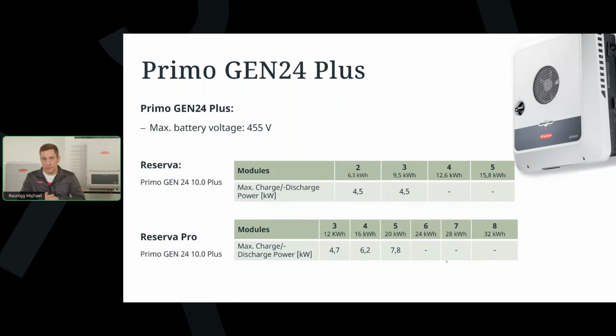Talking about the Primo Gen 24 Plus in detail, since this can be very interesting for single-phase markets, with the Primo Gen 24 Plus series, we have a maximum battery voltage of 455 volts. So that is our top level for the battery voltage, meaning that we get 2 compatible variants with the Reserva system. So with the existing battery system, we have the variants with 2 and 3 modules available. So that means from 6.3 to 9.5 kilowatt hours. However, the bigger systems with Reserva Pro are not compatible.